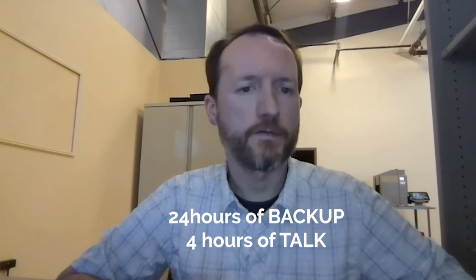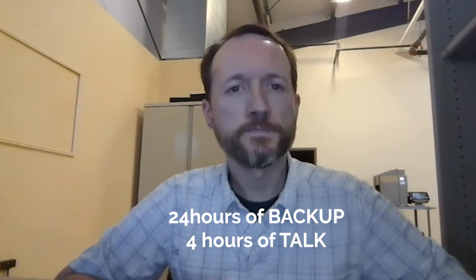Okay, so with this listing being a new standard for two-way communication systems, I'm curious if UL has any updated requirements, or what specifically are the requirements when you're powering one of these systems? Sure. So not new per se. The system needs to have a reliable power source, like every other life safety system. This means the power supply needs to meet UL 1481 requirements and have battery backup. The specific requirements for emergency communication are 24 hours of battery backup plus 4 hours of talk after the 24 hours.